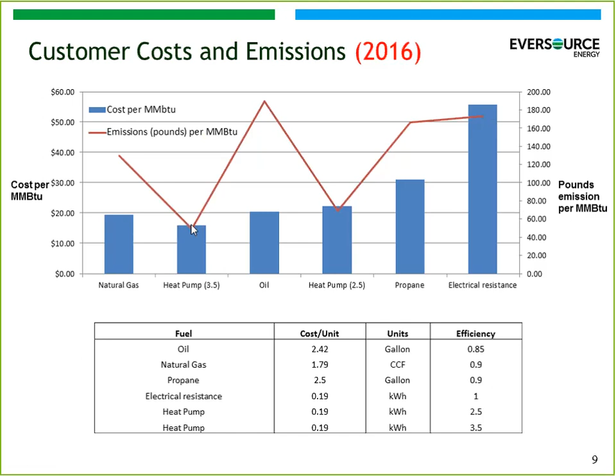You'll notice that even though natural gas and the geothermal heat pump are fairly comparable in cost, the ground source heat pump has the lowest emissions. That has to do with the heat pump being very efficient, so it's able to offset the fact that the generation fleet is not 100% efficient. In fact, it's more than able to offset that difference.